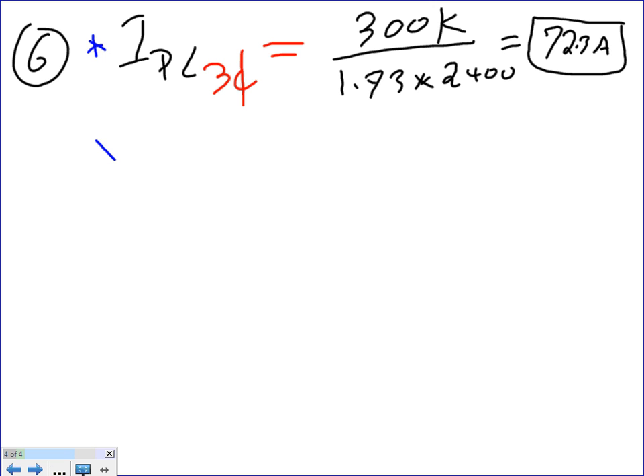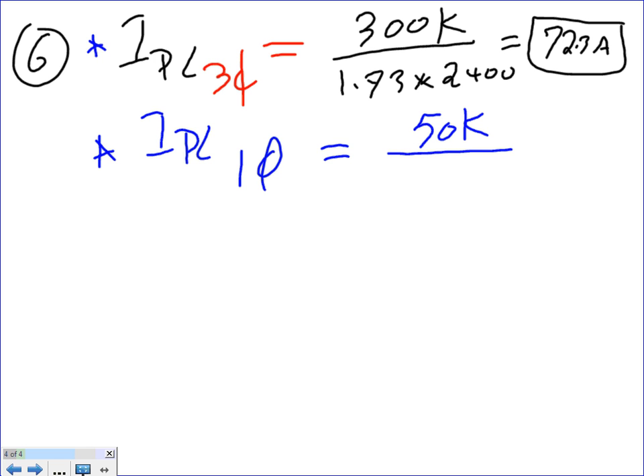I primary line, then I primary line single phase. This is piece of cake. You're going to take the single phase KVA, 50, divided by the voltage, 2400. Now do I multiply this by 1.73? No, it's single phase. So if you do that, you'll find I single phase is 21 amps.